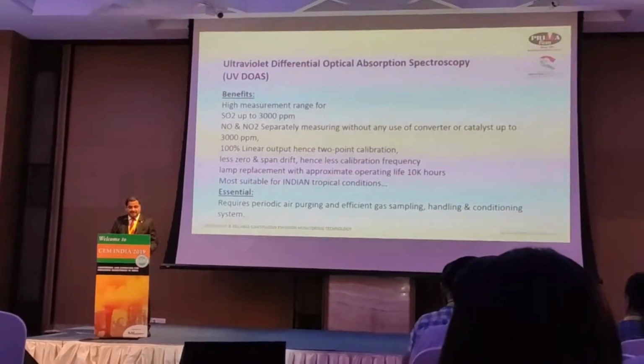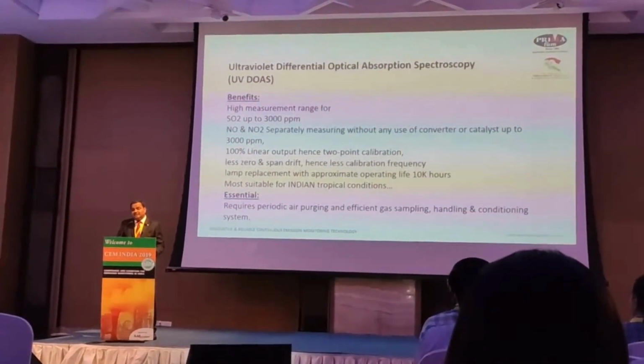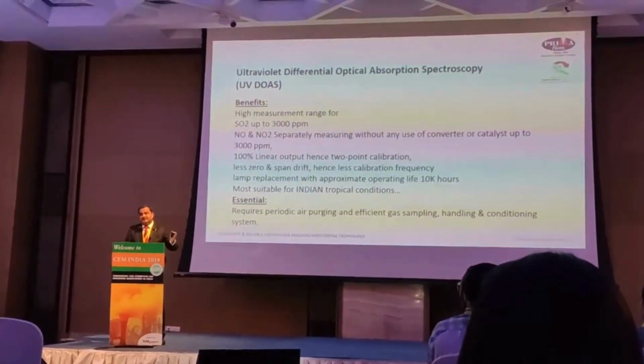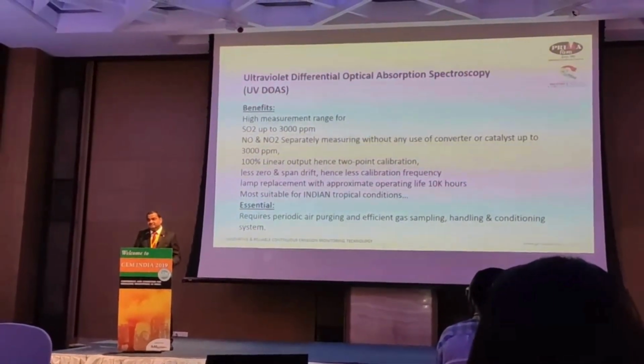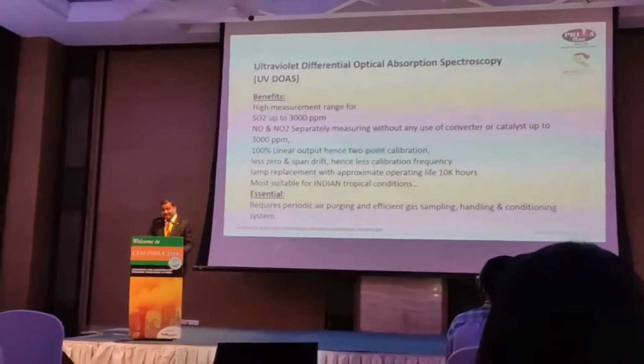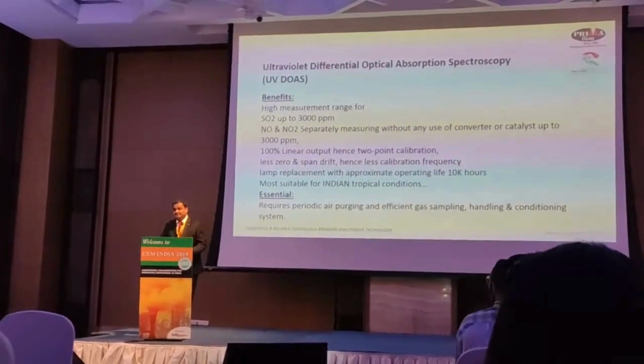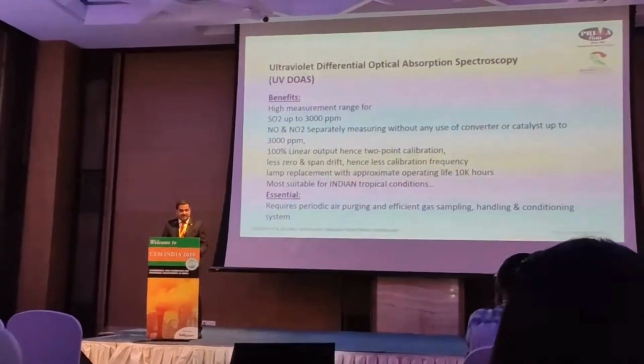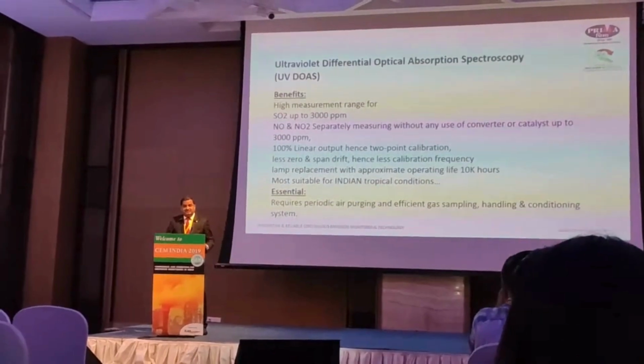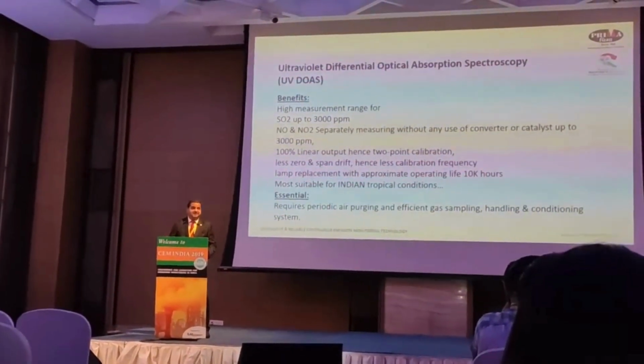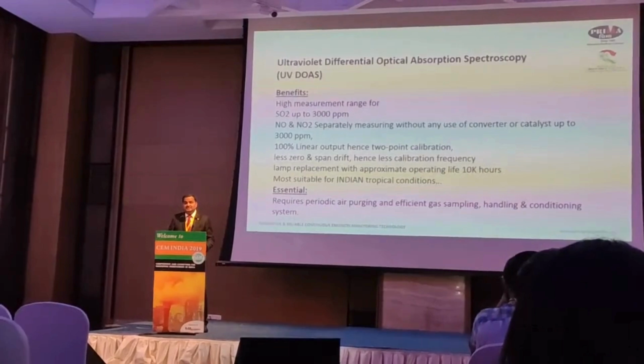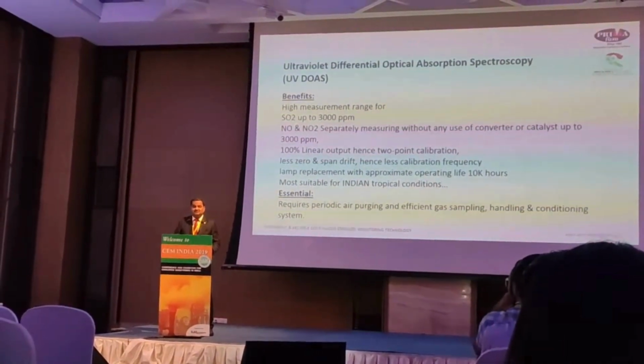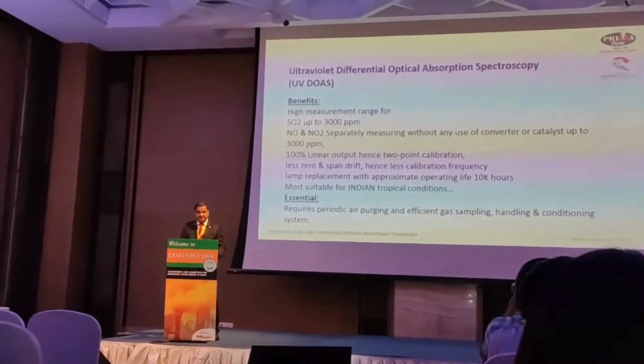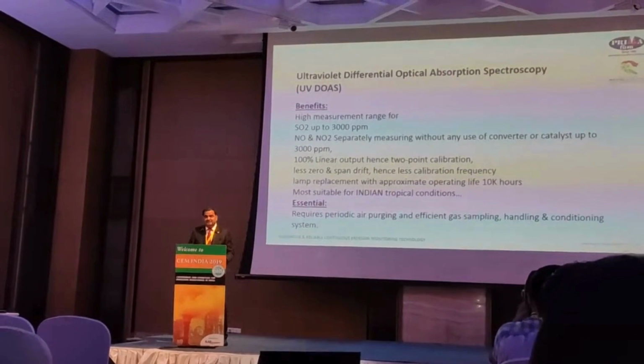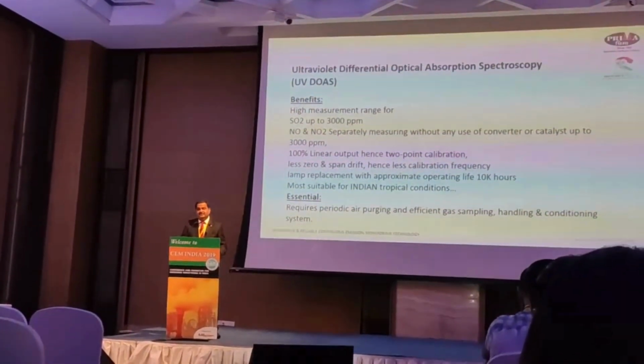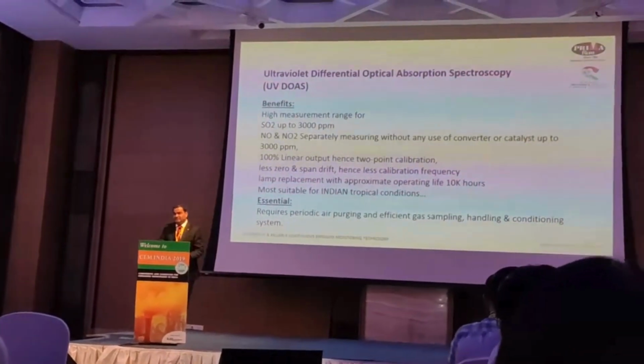In the laboratory, we have gone with what I mentioned as 100%; it comes to around 99 to 100% linearity as per the testing methodology we have used. Hence, we can consider that a 2-point calibration can be utilized here. As in the electrochemical sensors, as I mentioned, where some replacement of the sensor is needed, here we have a lamp. The typical life comes to around 10,000 to 11,000 hours. You need to change it. Again, we have seen and checked in the laboratory and in the field that we have made this equipment suitable for the tropical condition of India.